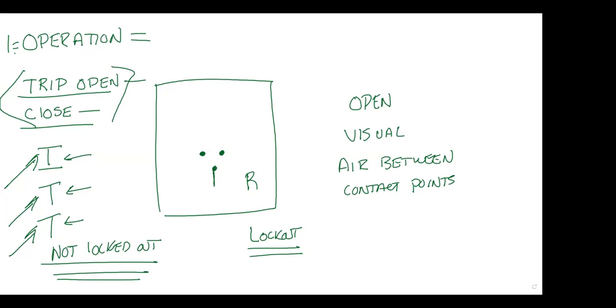As soon as you are hired, you can close a breaker if needed. True or false? False. There's only one thing that you have the capability to do as a brand new employee, and that is get a hotline work permit. Some companies will allow you, if it's an emergency, say you're driving down the boulevard and you see a wire on the ground, to call the dispatcher and say, I need you to open this breaker up. That's for safety. You cannot reclose. You cannot ask for a close. You can also get a hotline work permit. We'll talk about the procedures for that in just a moment.